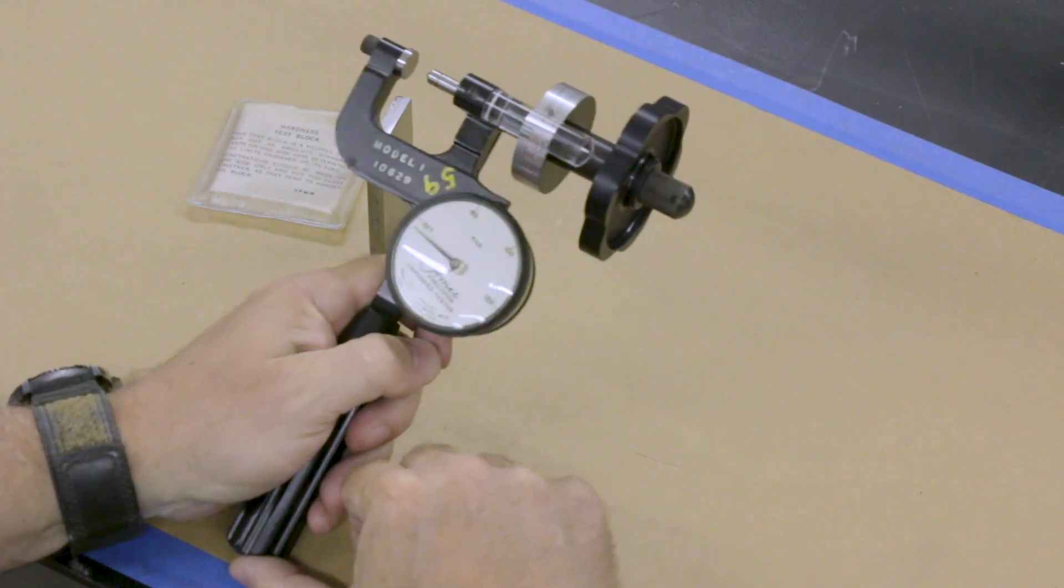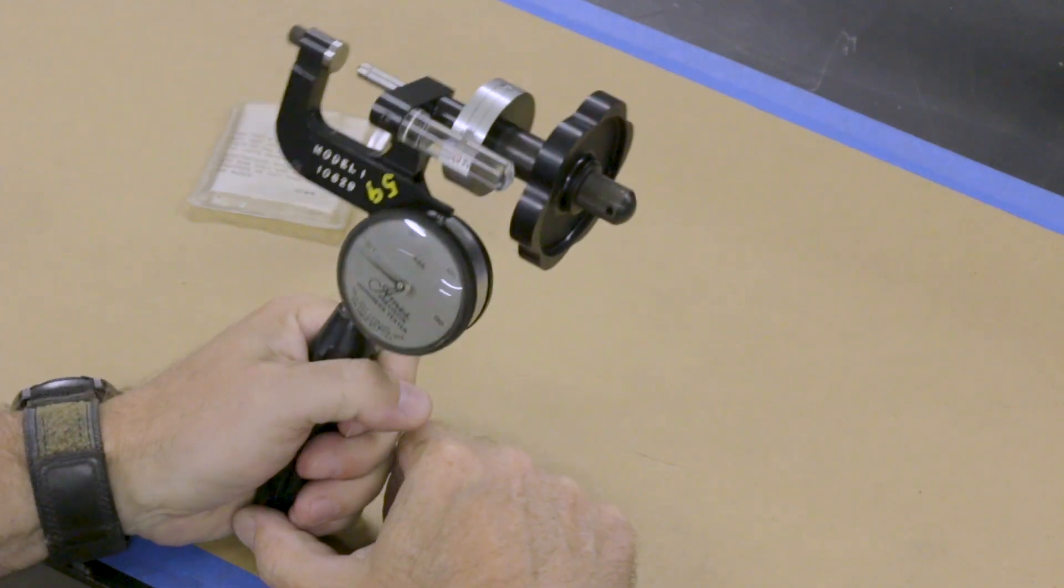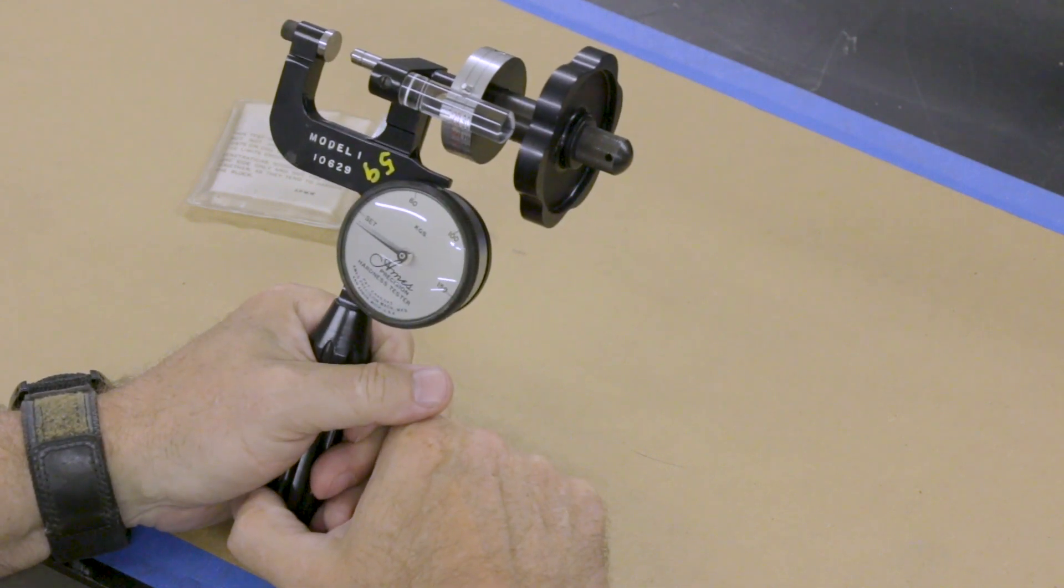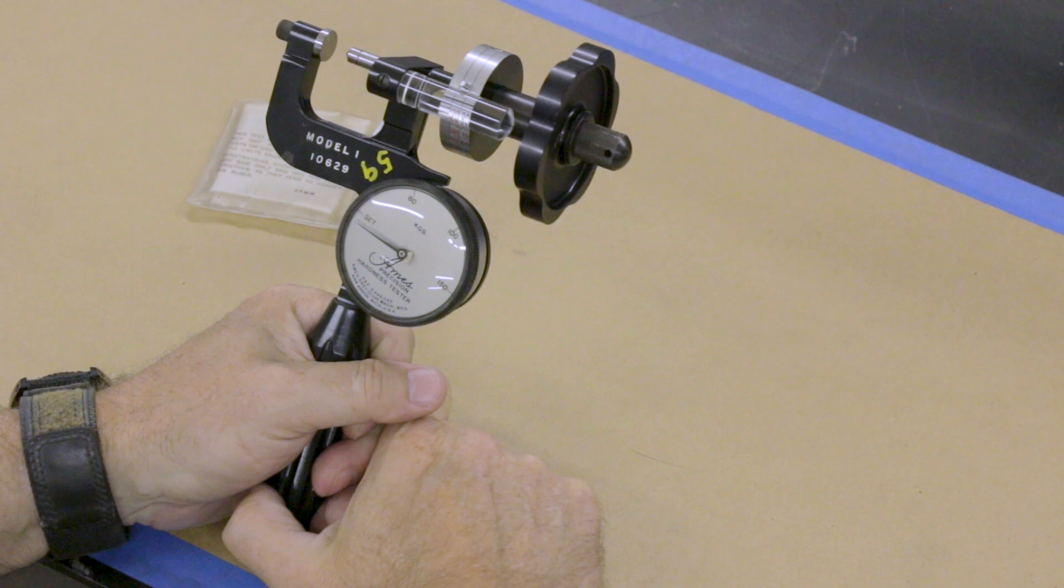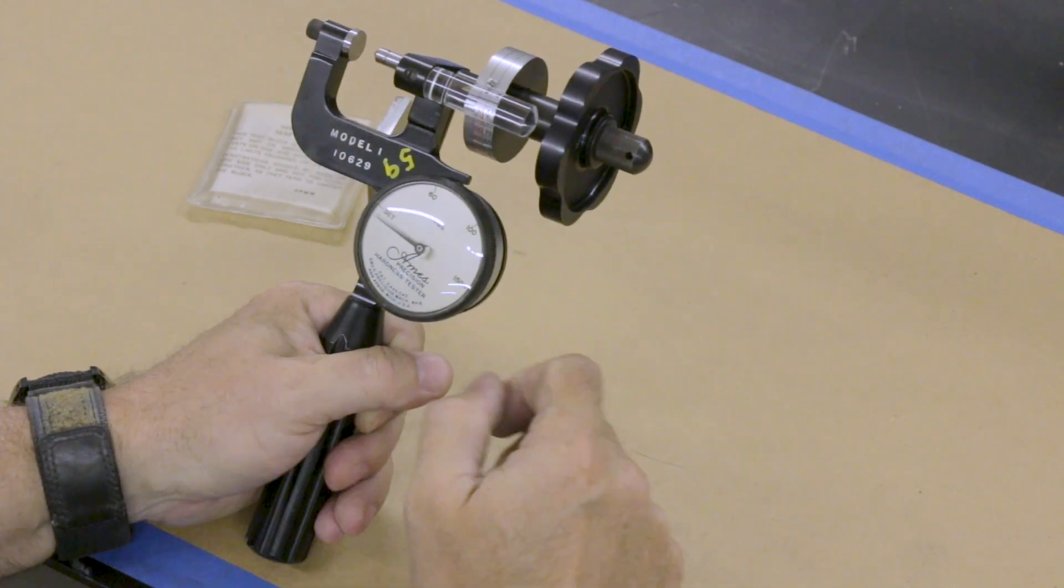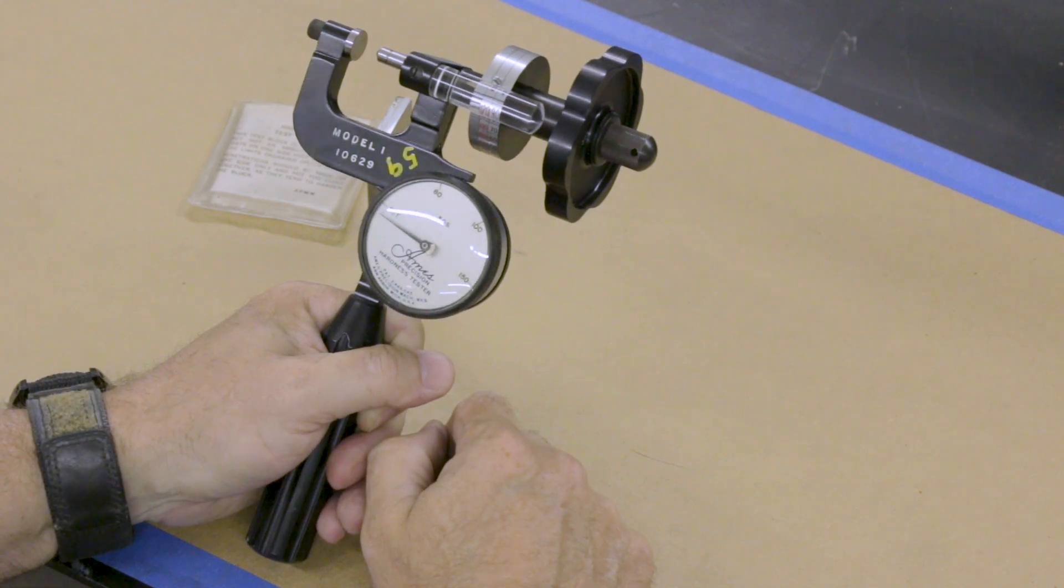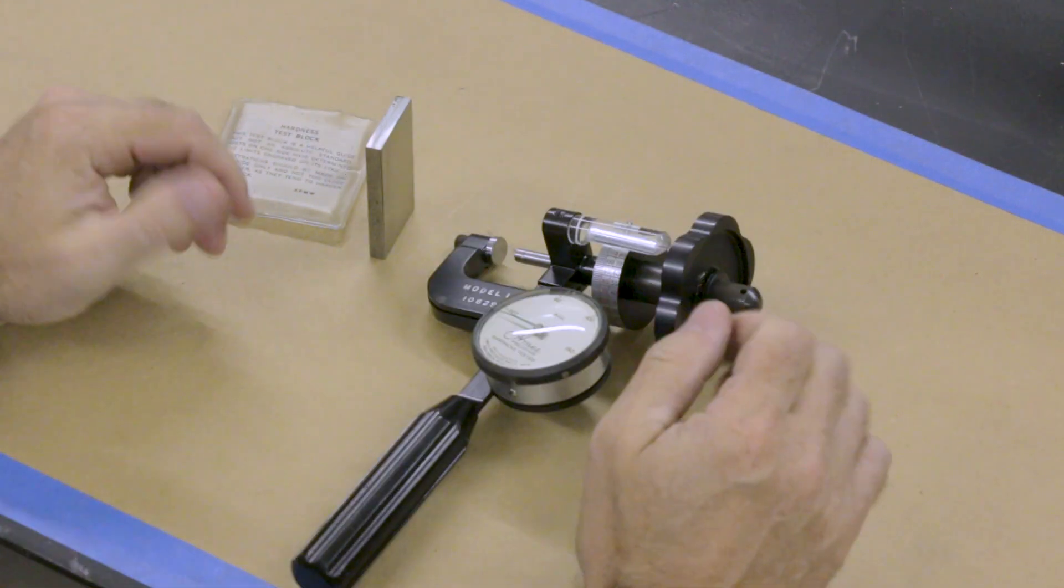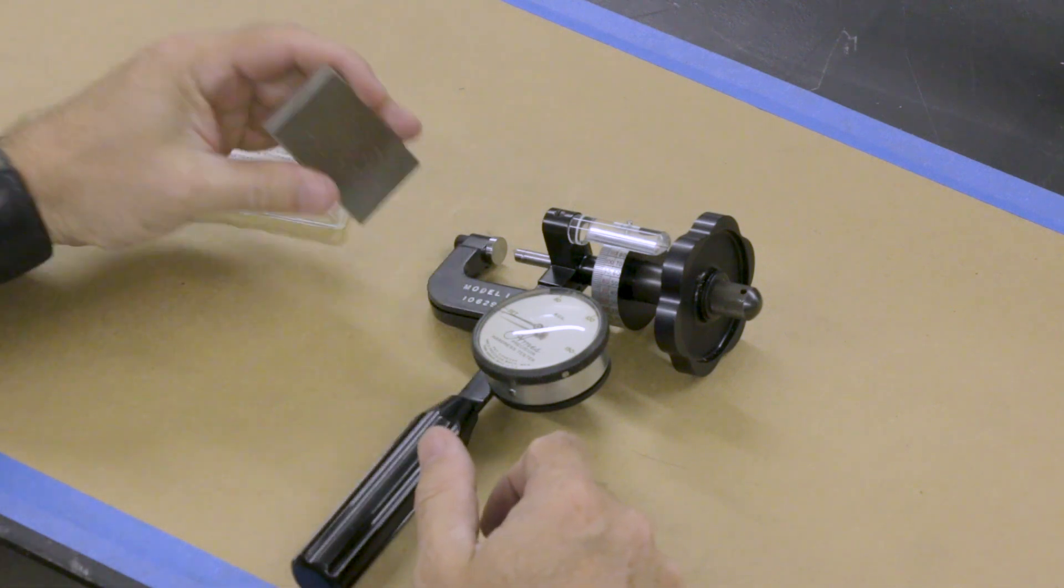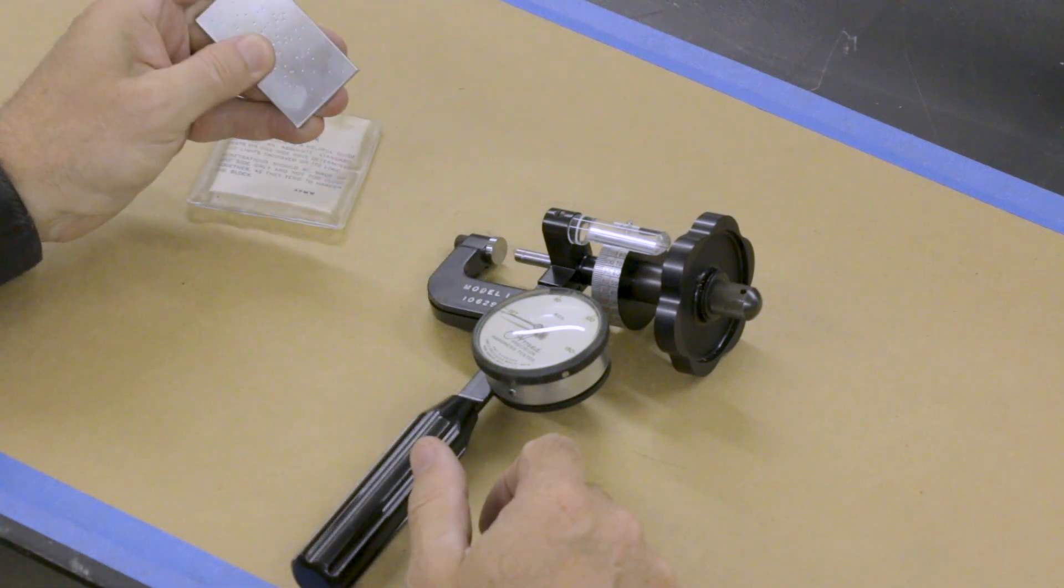And I probably could send it for calibration. But because it's always been consistently off by two, I just add those two to my knife blades. And it's off by two, not only on this 64 block, but on the other lower hardness block also. So then once I've taken the reading on my test block, then I'm ready to take a reading on my knife.